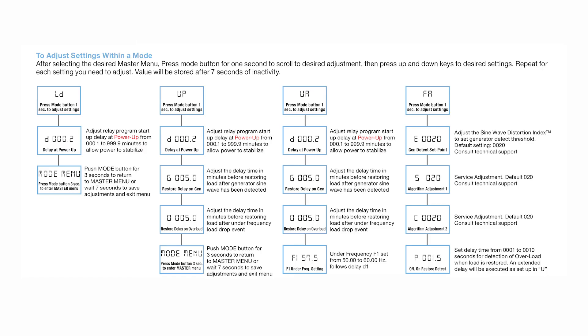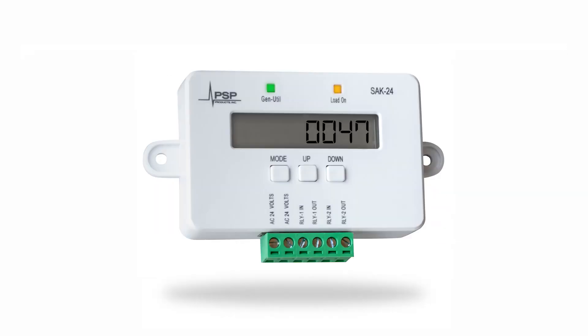The SAK24 can be set for generator load lockout so that the HVAC system is off whenever on generator power. This can be used to shut down the entire HVAC system or to lock out the strip heat on a heat pump system while allowing the heat pump and air handler to continue to run. This second application is very popular in the deep south.